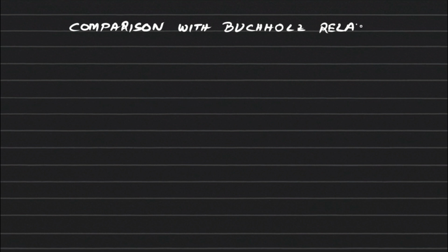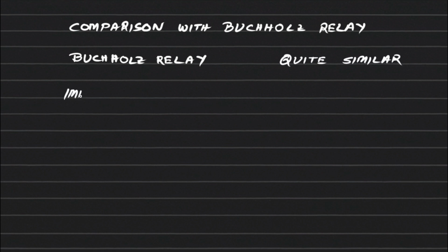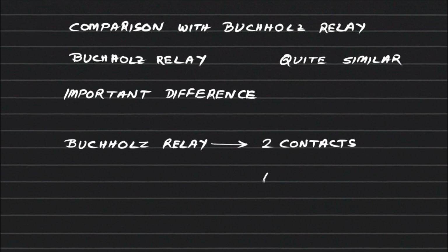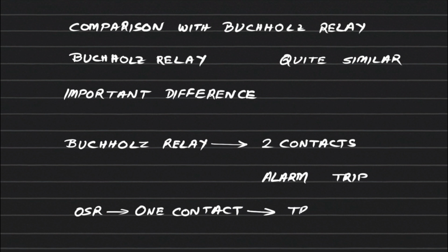Now, many of you might wonder, isn't this similar to a Buchholz relay? Yes, the OSR looks quite similar to a Buchholz relay, but there is one important difference. The Buchholz relay has two contacts, one for alarm and another for trip. The OSR, on the other hand, has only one contact, the trip contact. It does not have any alarm contact. Let's understand how the OSR works.